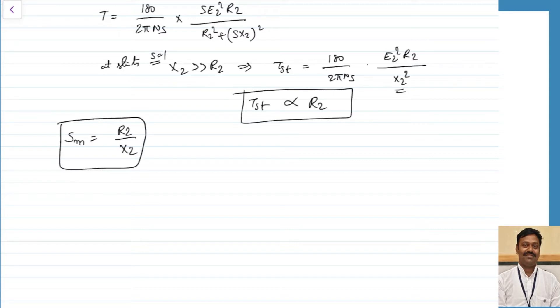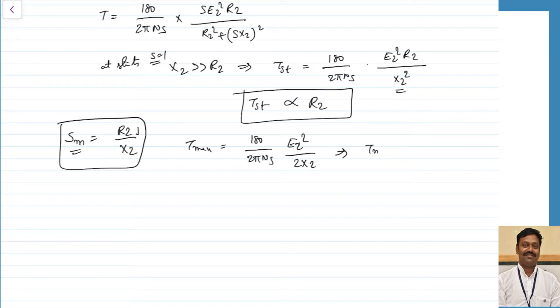If the ratio R2/X2 is more, the slip corresponding to maximum torque will be more, meaning maximum torque occurs at a larger slip. If R2 is less, the slip corresponding to maximum torque shifts towards synchronous speed. The maximum value of torque equals (180/2πNs) × E2²/2X2, so maximum torque is inversely proportional to reactance — if reactance is more, maximum torque will be less.